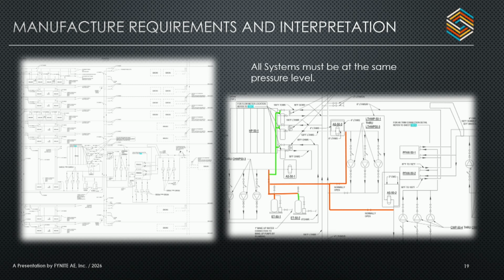So one of the design considerations that the engineer of record took into consideration was a statement in the manuals that said that all systems must be at the same pressure level. And historically, we've always put this place of zero pressure drop on the pump suction. Now, our configuration for this plant was that we drew through all the chillers simultaneously. So we don't pump into the chillers, but we draw through them. And what ended up happening in this case was that because the point of zero pressure drop is on the pump suction and not on the chiller manifold, the pressure drop between all the chillers is significantly different at different flows. So if you have one of the chiller headers at like 90 GPM, there's essentially no pressure drop in the system. But if we're running at 350 GPM on the same exact header at a different time, you could have 3 or 5 PSI difference between what the header sees and what the pump suction sees.